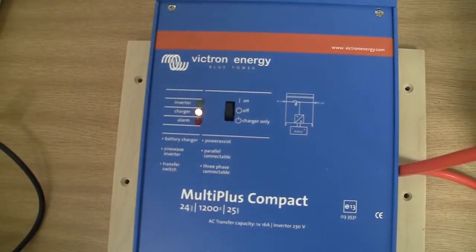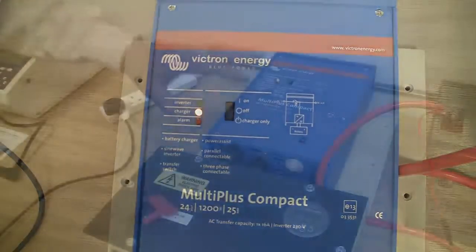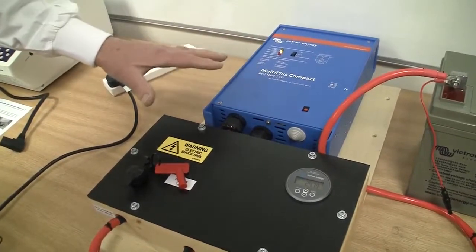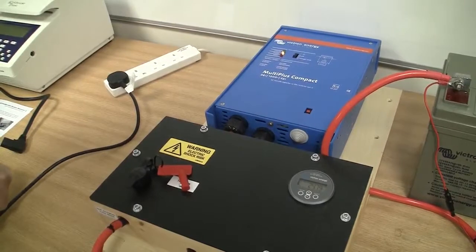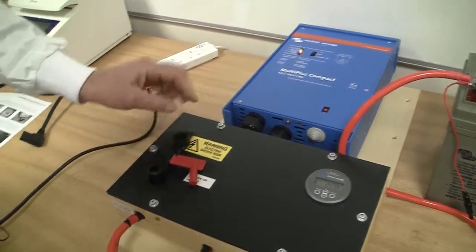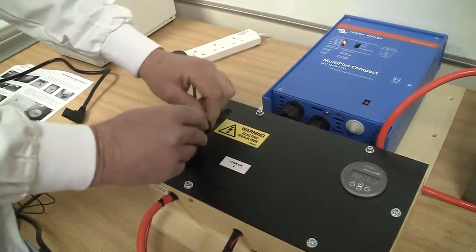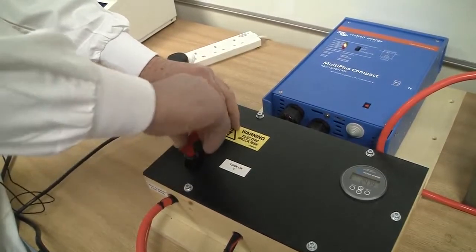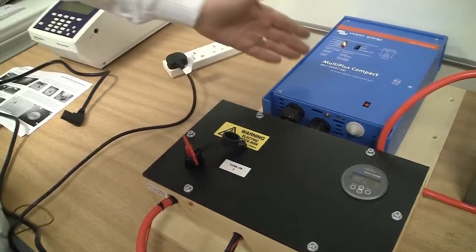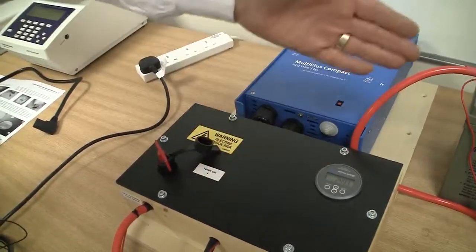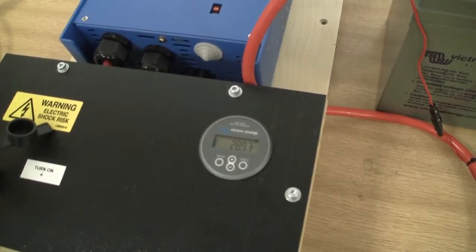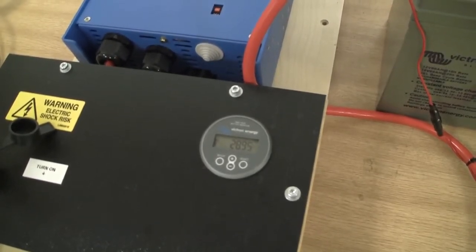This charge mode is not charging the batteries because at the moment with this key this charger is disconnected from the batteries. The next stage is to actually put the key in and allow the electricity to reach the batteries. So the key goes in and turns clockwise and there we have the electric flowing through into the batteries. This can be seen by the monitor is now increased from 24 and above showing the electricity going into the batteries.